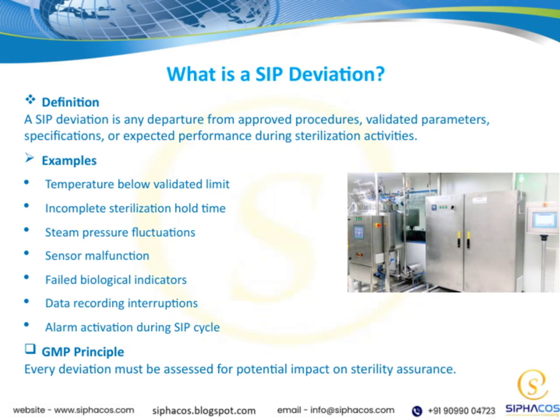Let's talk about what a SIP deviation actually means. It's any time something strays from the approved procedures or expected conditions during sterilization. That could be the temperature dropping below the validated limit, the sterilization hold time not being met, or steam pressure fluctuating unexpectedly. It might also involve sensor malfunctions, failed biological indicators, interruptions in data recording, or alarms going off during the cycle. Importantly, every deviation has to be carefully evaluated to understand its impact on sterility assurance.